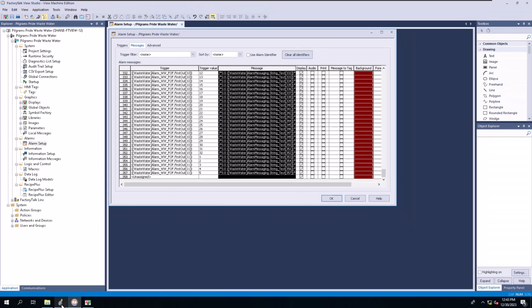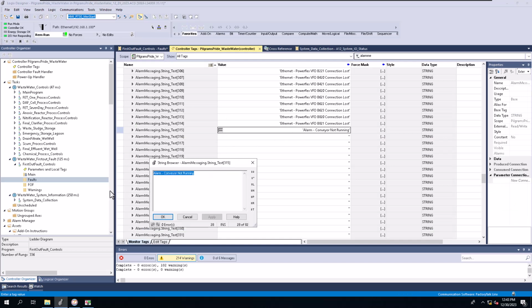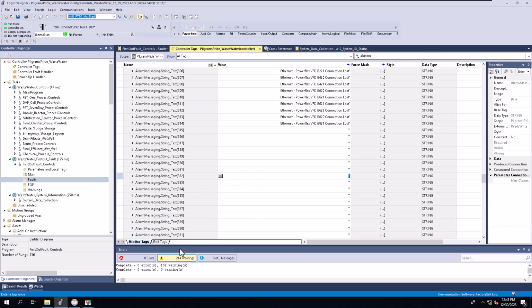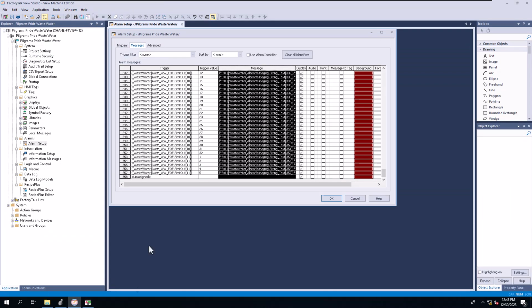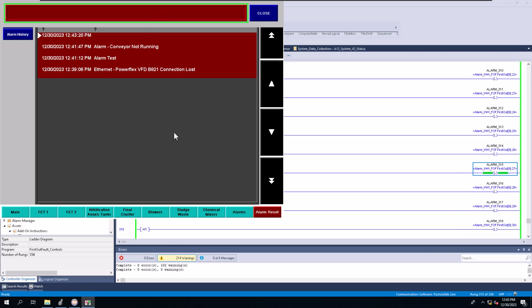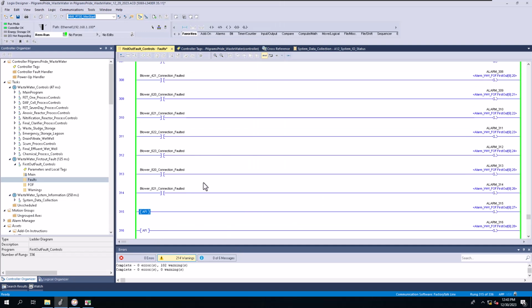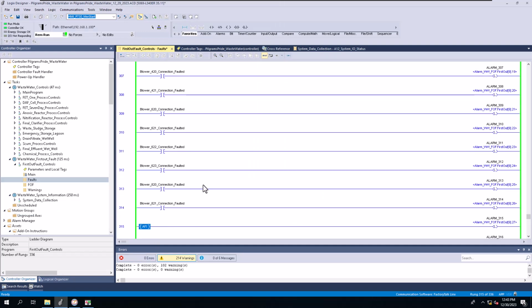When you can save yourself some time, do this on the front end, and then go ahead and change it literally in 5 seconds. Like, let's just say now I want to take this back because I'm not actually using it. So now what's going to happen is if I trigger the bit 15, nothing is going to happen. I mean, it's basically going to pop up, but it's not going to have an alarm text because I eliminated the alarm text. So you see how simple and easy that was, right? And I can keep that AFI'd out so that I don't use it inside of my PLC logic. So it's all a simple PLC transition instead of constantly having to edit your FactoryTalk ME application and then make a runtime and download to it.